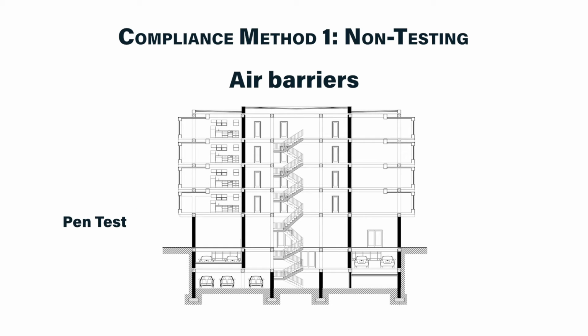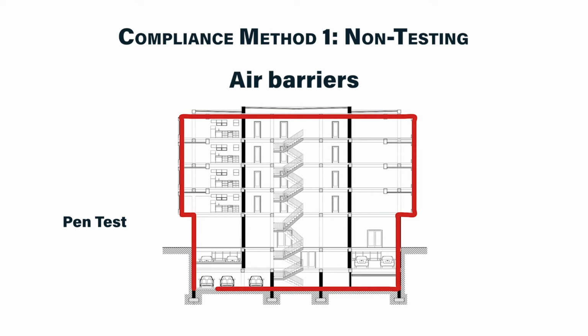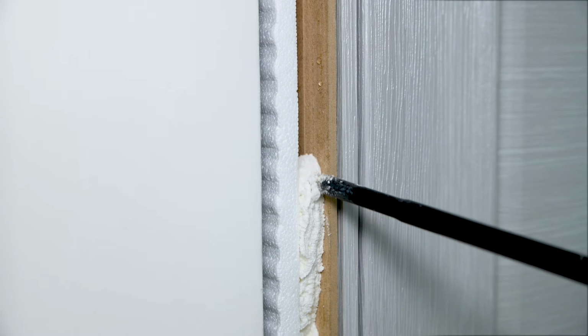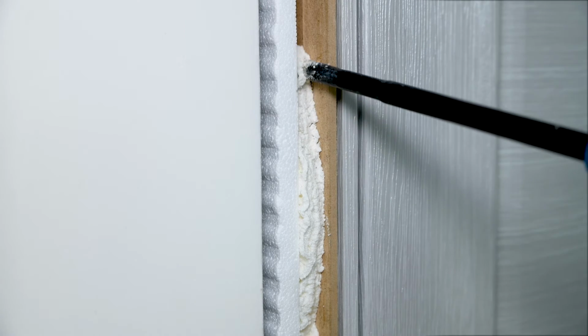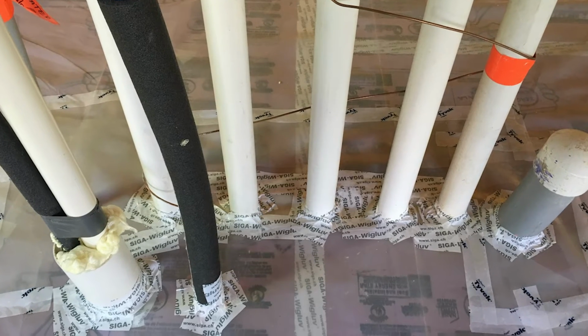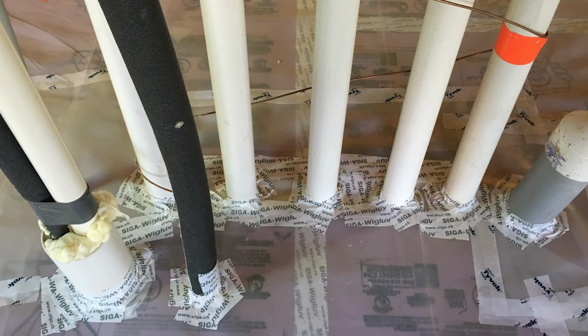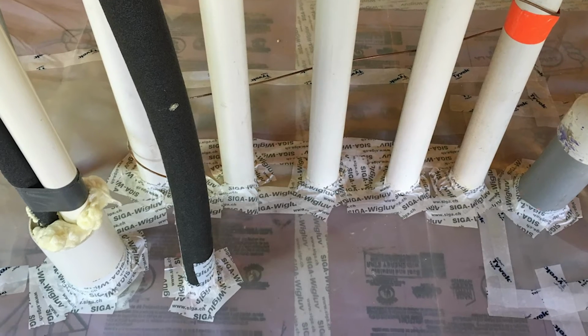Try a pen test to confirm your air barrier is continuous. Can you follow the identified air barrier layer throughout the building thermal enclosure without lifting your pen? In addition, care should be taken to make sure joints and seams are sealed, penetrations are caulked, gasketed, or otherwise sealed in a manner that is compatible with the construction materials and location.